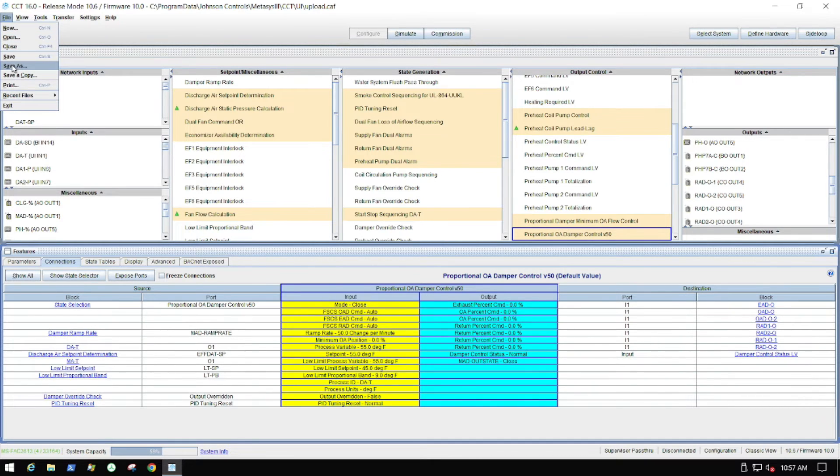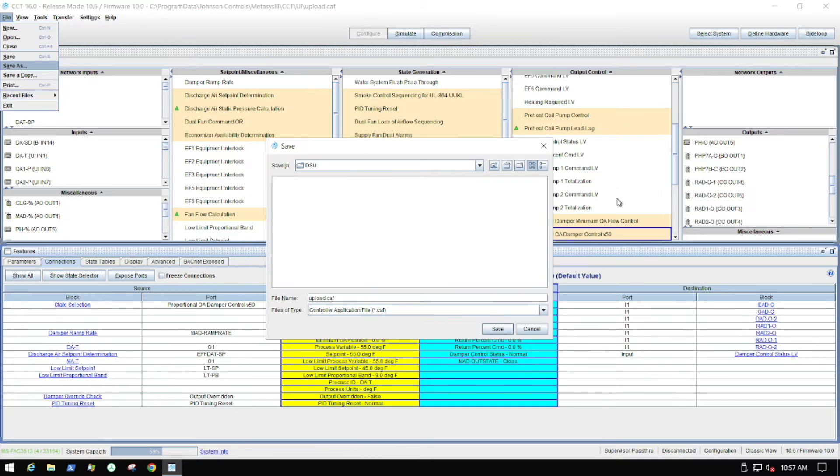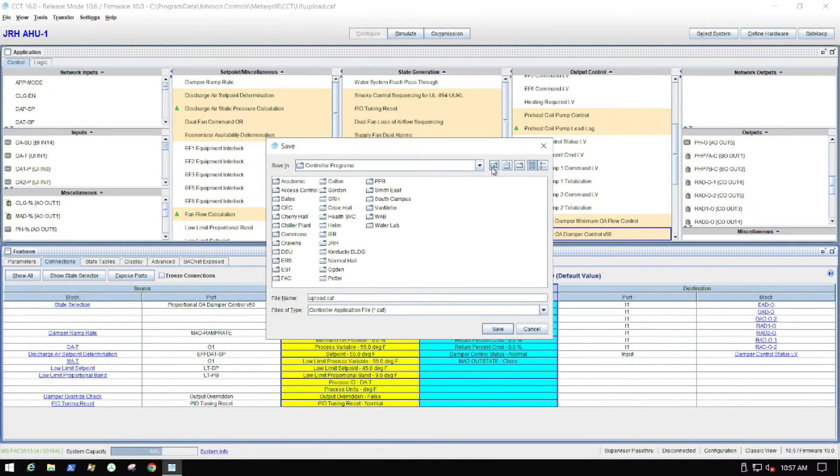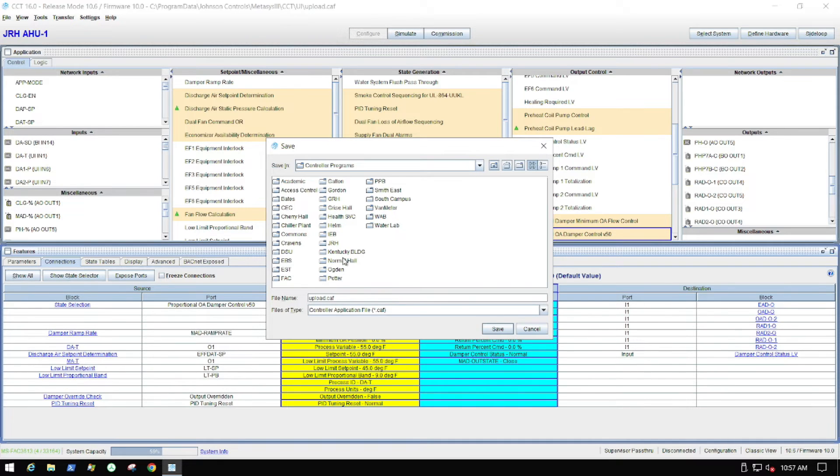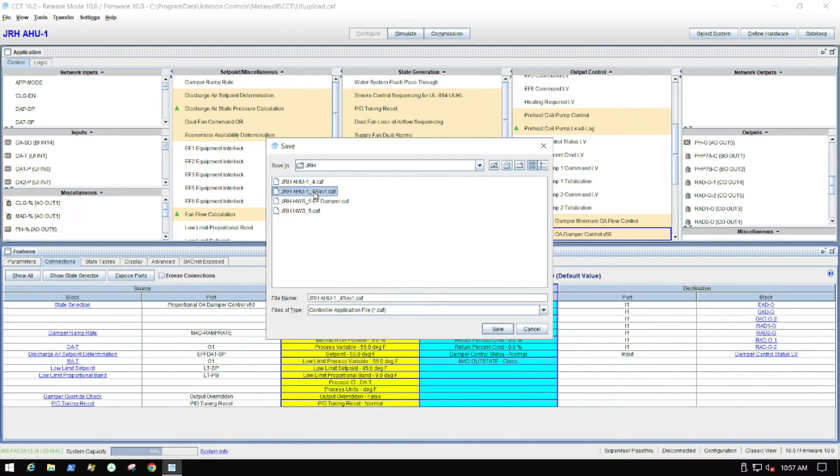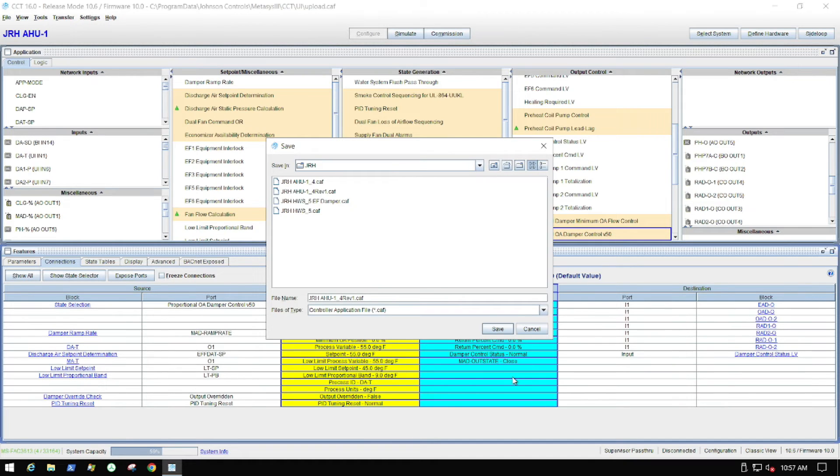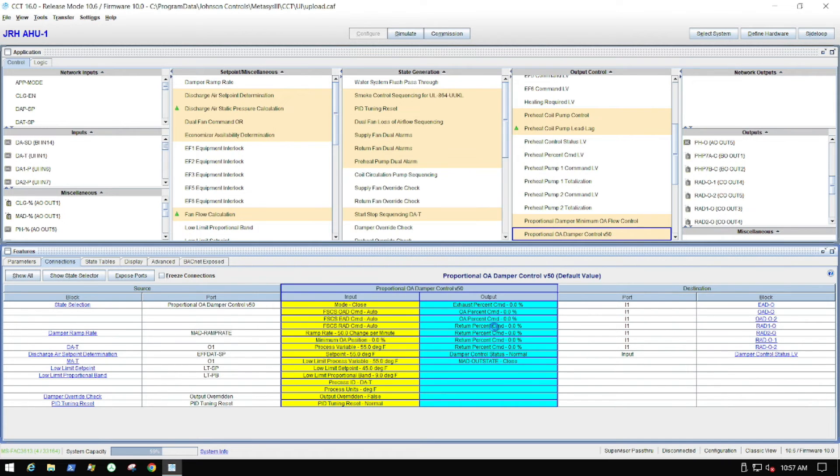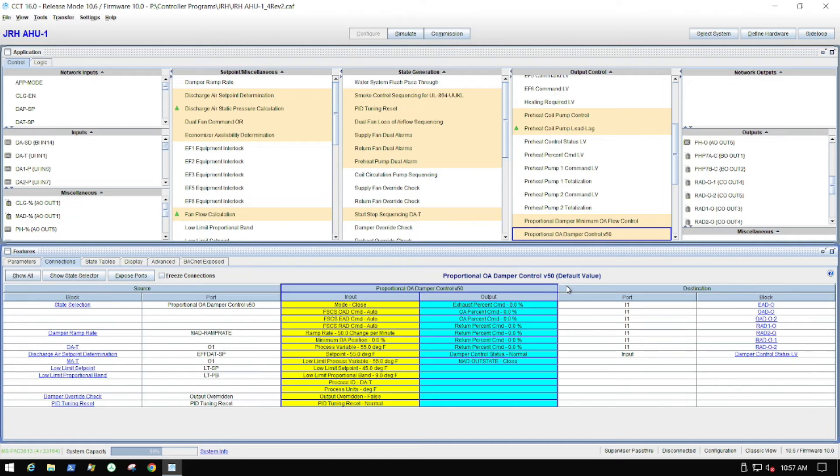what you want to do, I want to make sure that I save a copy of my program. Always save a copy of the original before you go in and start modifying things because if something were to happen and you can't go back to your original program, you could have your equipment down for much longer than necessary. Again, this was an air handler that I could only have down for a brief period of time because it's literally the only unit that serves an entire building.